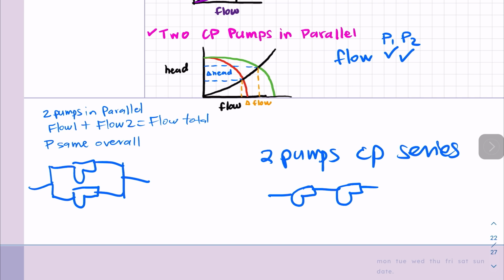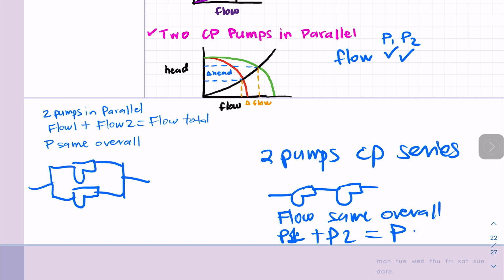Now, when pumps are connected in series, they're installed so that the discharge of one connects to the suction of the other. This means the flow rate of each pump is the same, the flow is the same overall. But as a result, the total pressure of the system is the sum of the pressures at each pump, so pressure 1 plus pressure 2 equals the final pressure.